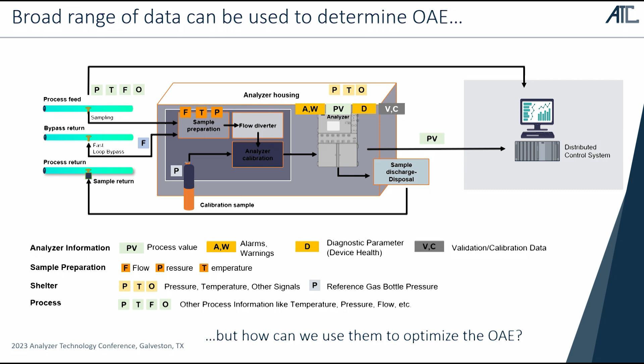So imagine a gas chromatograph. When you do troubleshooting, you go to the gas chromatograph, you may be looking at the response factor, the retention time, the chromatogram and so on, but you're not using it in a continuous way, right? You're using it if you have a troubleshooting. So we see that we should use all this data to optimize the performance of the analyzer in the field. So let's talk about some examples to make it very concrete.